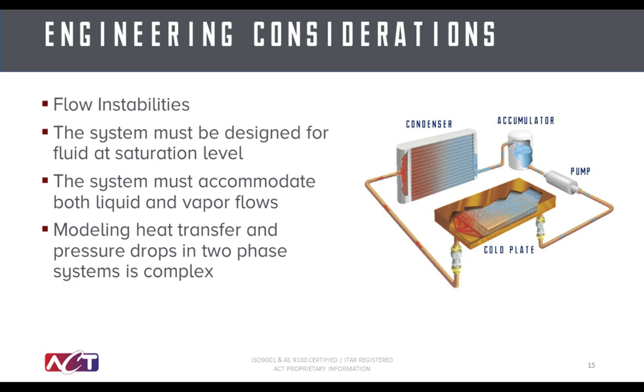Flow instabilities can also occur in parallel channels or parallel evaporators. As you saw in the video earlier, ACT has developed mitigation techniques for ensuring that all of the evaporators and all of the channels receive the same amount of flow under all conditions. Another concern with two-phase systems revolves around the modeling of the heat transfer and pressure drop in the system to get an accurate prediction of the performance. Two-phase heat transfer coefficient correlations and pressure drop correlations are notoriously inaccurate. Over the years, ACT has developed numerous modeling techniques to provide higher fidelity modeling approaches for a wide range of different applications.